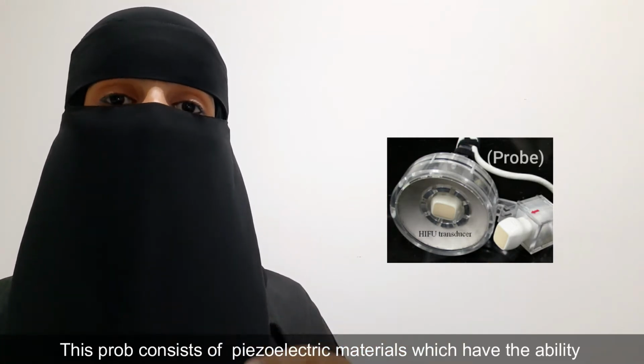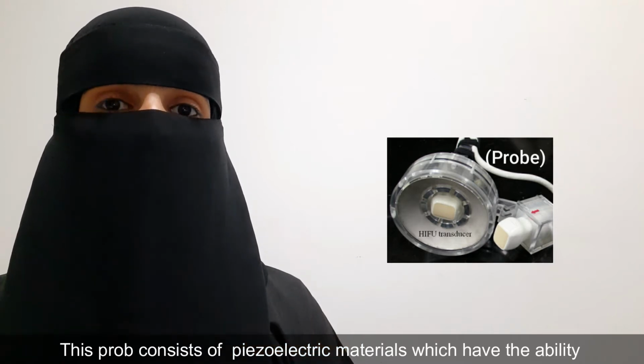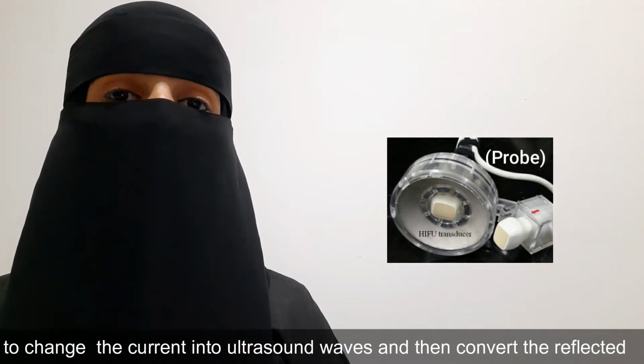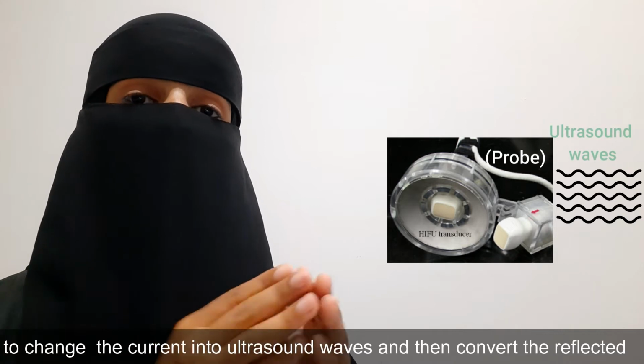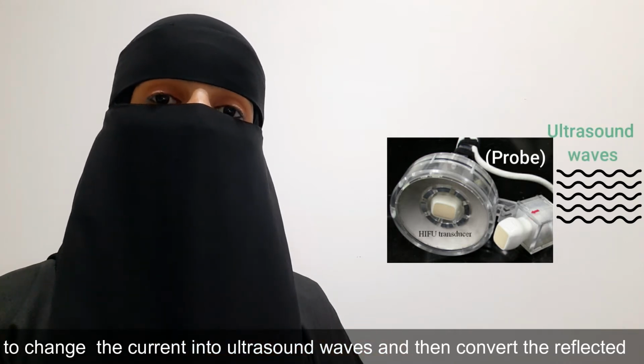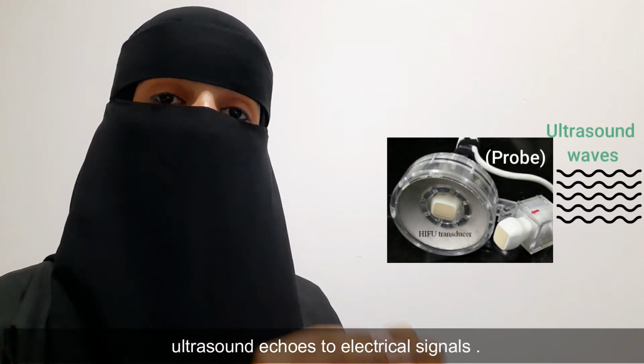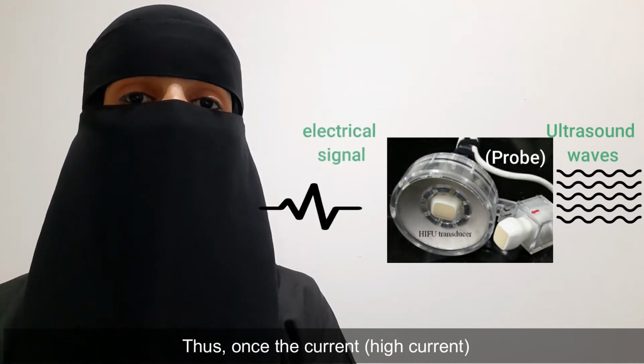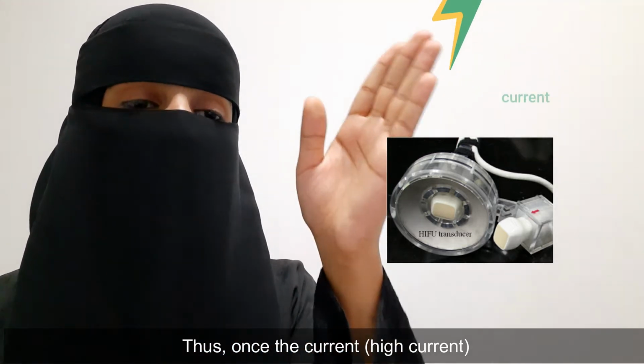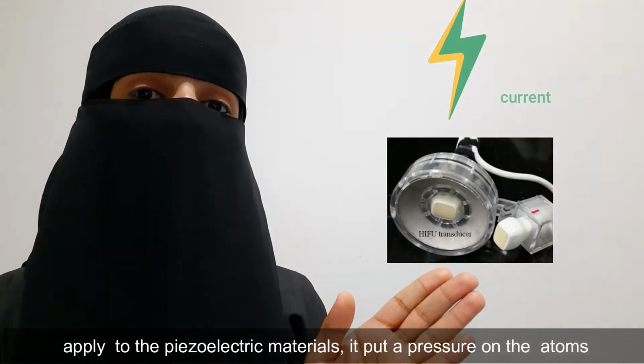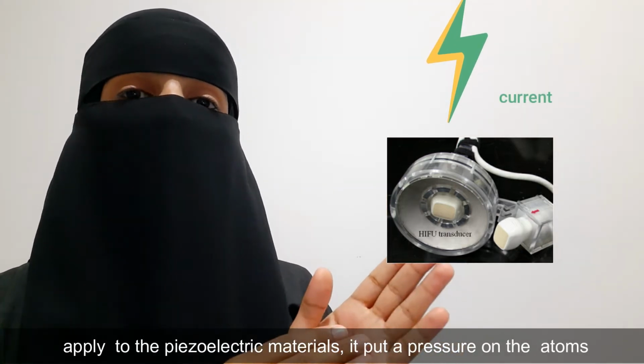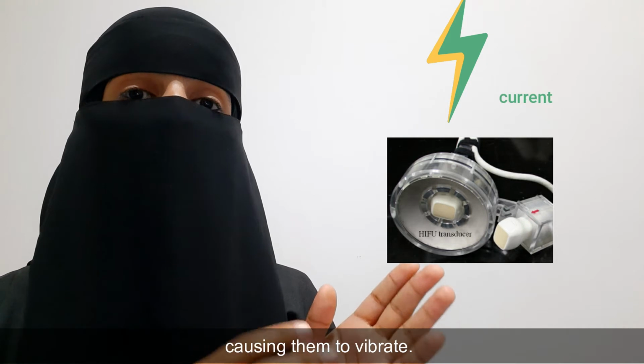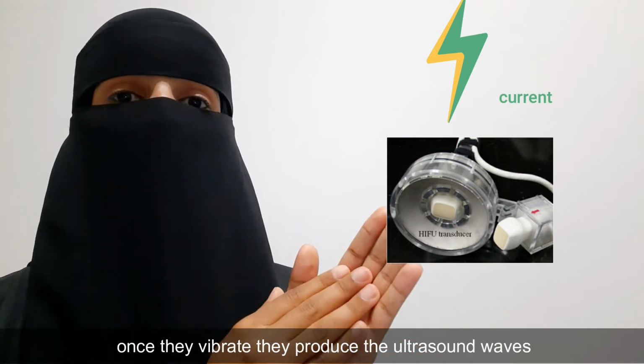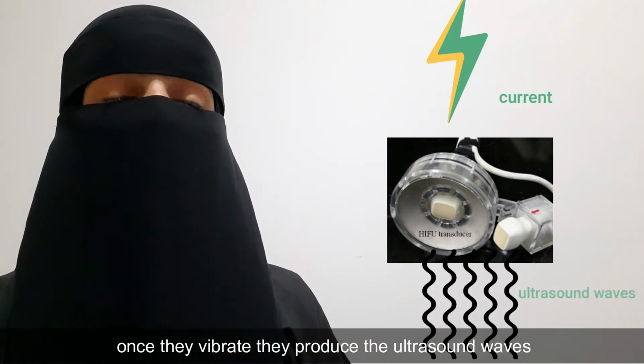This probe consists of piezoelectric materials which have the ability to change the current into ultrasound waves and then convert the reflected ultrasound echoes to electrical signals. Once the high current is applied to the piezoelectric materials, it puts pressure on the atoms, causing them to vibrate. Once they vibrate, they produce the ultrasound waves.